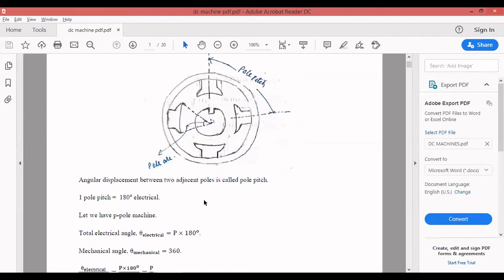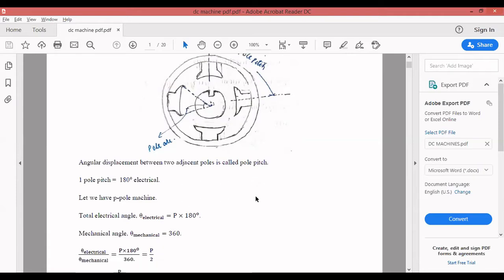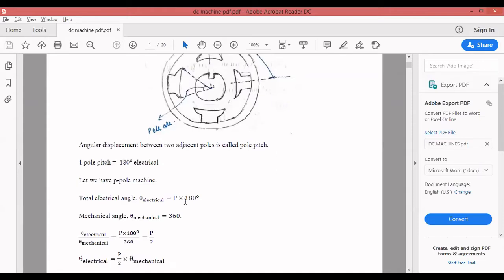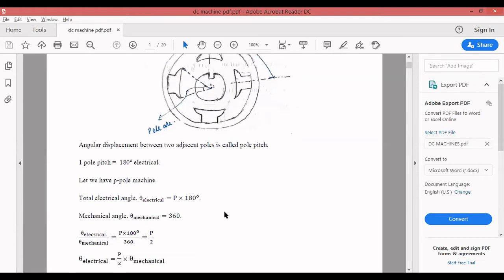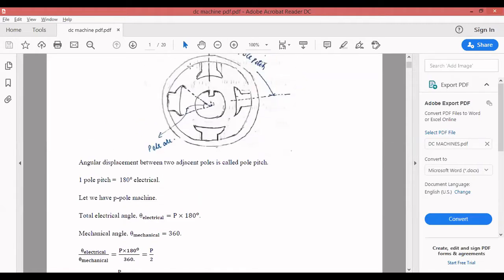One circumference is equal to 360 degrees mechanically, but not with respect to electrical degree. One pole pitch is the angular displacement between two adjacent poles. One pole pitch equals 180 electrical degrees — not mechanical 180 degrees. In mechanical terms it is around 90 degrees, but in electrical terms it is 180 degrees electrical. Here we have four poles, so the total electrical angle theta_electrical equals P into 180. Mechanical angle means the entire circumference, which is 360 degrees.